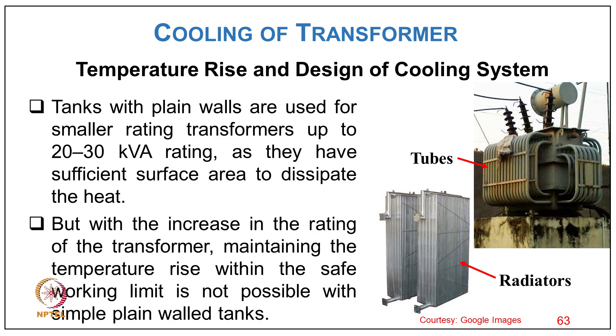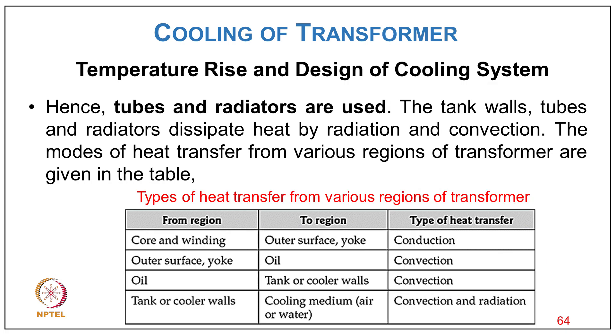For temperature rise and cooling system design: tanks with plane walls are used for small ratings up to 20–30 kVA as they have sufficient surface area to dissipate heat. With increasing rating, maintaining temperature rise within safe working limits is not possible with simple plane wall tanks. Hence tubes and radiators are used, and the tank wall, tubes, and radiator dissipate heat by radiation and convection.